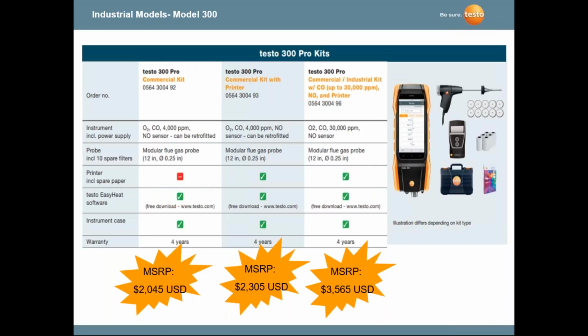The Model 300, we call it the Industrial Pro version, is similar in design and appearance. It's orange, but it accommodates up to 3 sensors: oxygen, carbon monoxide, and the NO sensor. The first two versions there, you see 92 and 93 part numbers. You can upgrade the 300 at a later date with the NO sensor. If you immediately need to measure NOx, you can get the third version, which is a top-of-the-line version, which the NO sensor is already installed.